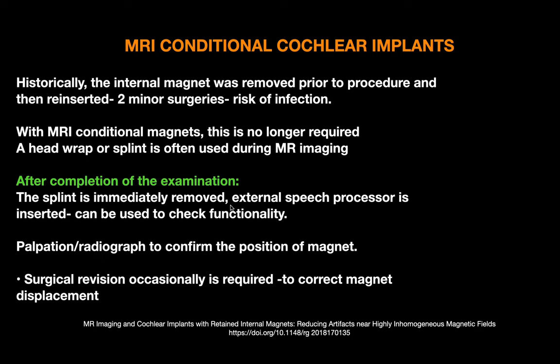After MRI completion, the splint is immediately removed and the external speech processor is reinserted and checked for functionality. One radiograph or palpation should be performed to confirm the position of the magnet. Surgical revision is occasionally required to correct magnet displacement if present.